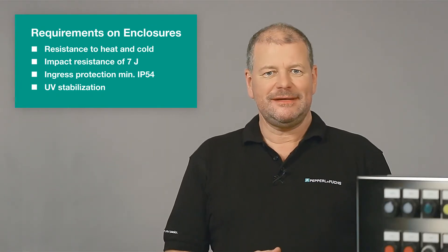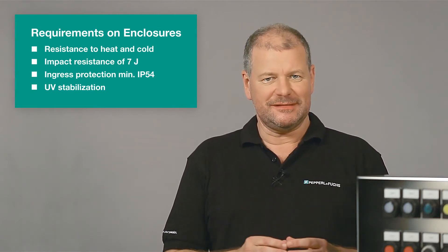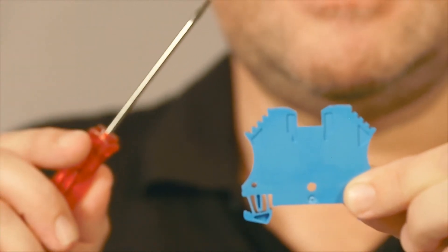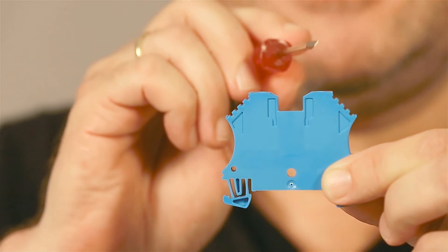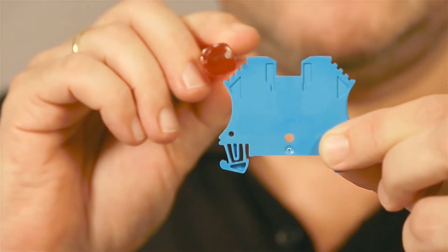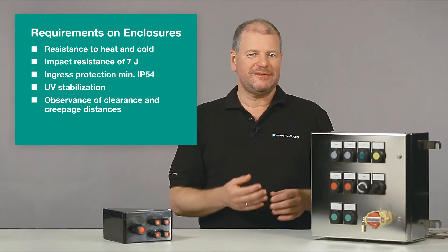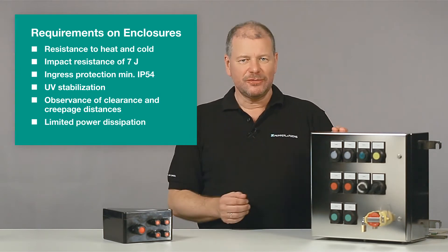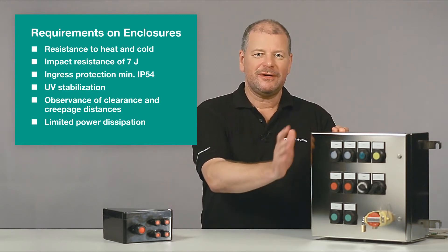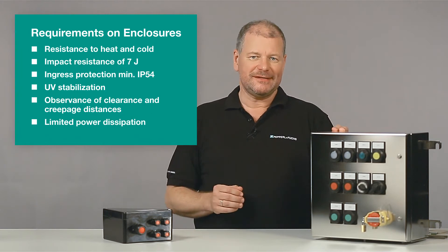Very important for Ex is the observance of appropriate clearance and creepage distances. The clearance distance is the shortest airline distance between two potentials. The creepage distance is the shortest distance along the surface of the specific components. The power dissipation inside the enclosure has to be limited sufficiently; no spot of the inner or outer surface must reach the ignition temperature of the surrounding gas atmosphere.